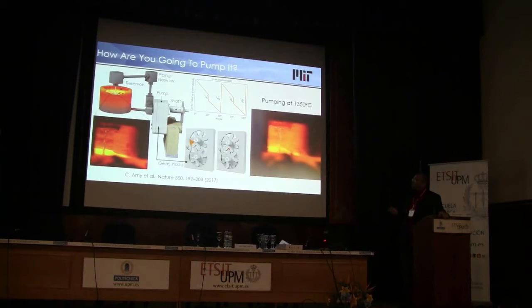One of the main things that happens in a system like this is all the components grow thermally — you get thermal expansion. So we have a bunch of hot components, and then a series of connecting shafts where there's a temperature gradient as it cools, and the motor stays in the cold region. So you have a cold motor and hot moving components in the hot zone. One of the key things that happens is you get thermal growth, which causes misalignment of the pump — the first few times we tried it, it broke itself apart.